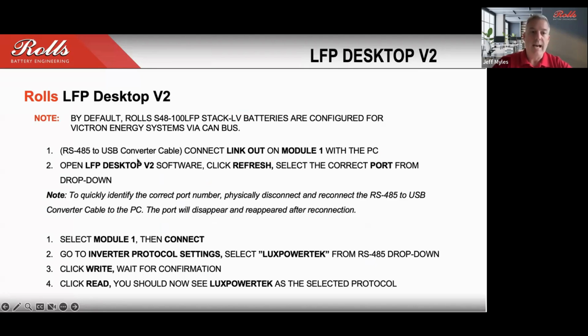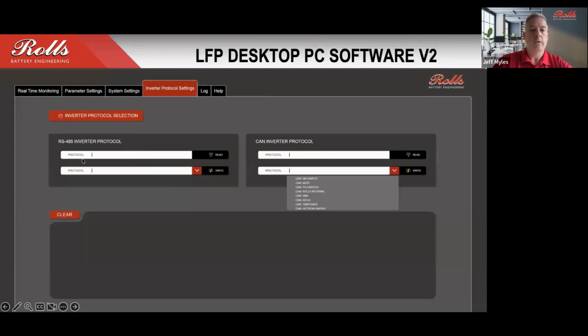What we initially had was essentially a PC software where you load the software onto your computer. You use a cable, which is an RS-485 to USB cable, which is supplied in one of the boxes. And that allows you to connect to the primary battery in this stack. And then you can apply the inverter protocol that you wish to set up. So for example, if you're setting up with LuxPower, you would pick that from the dropdown, write it to the battery, and then you can verify that it has been written to the battery once that's been done. When you're using that particular software, you're going to see, whoops, sorry, I skipped.